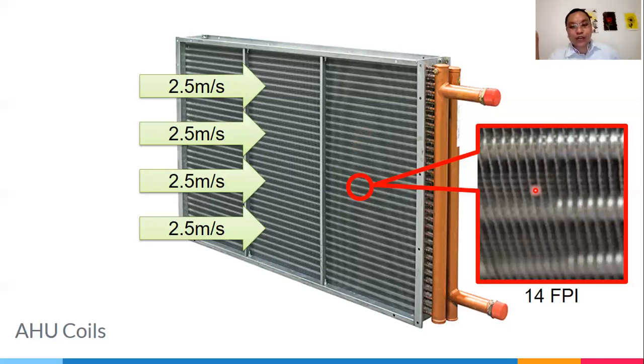Sa coil manufacturing, no, there's 8 fins, there's 12 fins, and there's 14 fins. Okay. The lower the fins, the lower the heat exchange. The higher the fins, the better heat exchange. Kaso nga lang, kapag higher yung fins mo, ibig sabihin, higher din yung pressure drop mo. Pero mas maganda naman yung efficiency mo. If you lower the fins, you will have less pressure drop, but you will also have less efficiency doon sa heat transfer mo.